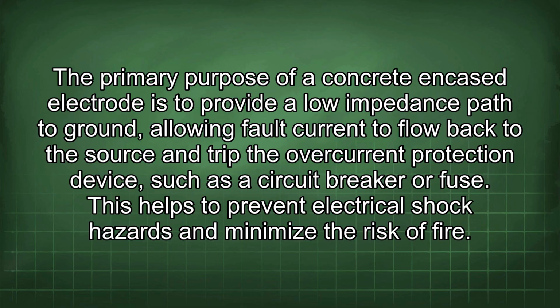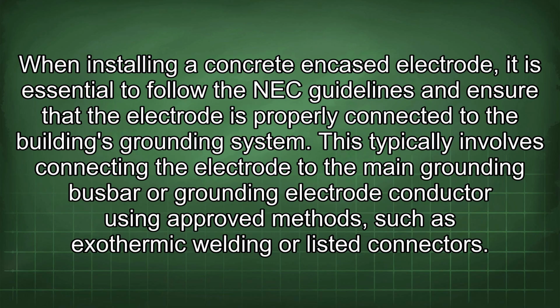The primary purpose of a concrete encased electrode is to provide a low impedance path to ground, allowing fault current to flow back to the source and trip the overcurrent protection device, such as a circuit breaker or fuse. This helps to prevent electrical shock hazards and minimize the risk of fire. When installing a concrete encased electrode, it is essential to follow the NEC guidelines and ensure that the electrode is properly connected to the building's grounding system. This typically involves connecting the electrode to the main grounding busbar or grounding electrode conductor using approved methods such as exothermic welding or listed connectors.